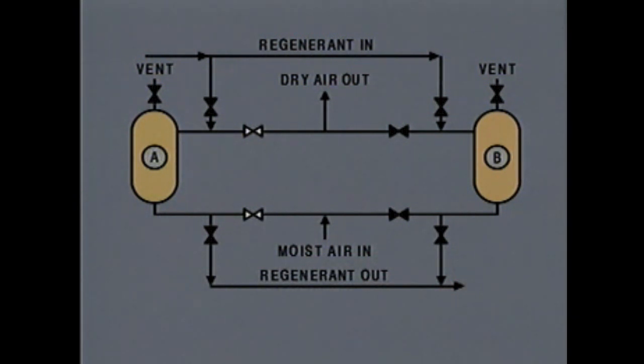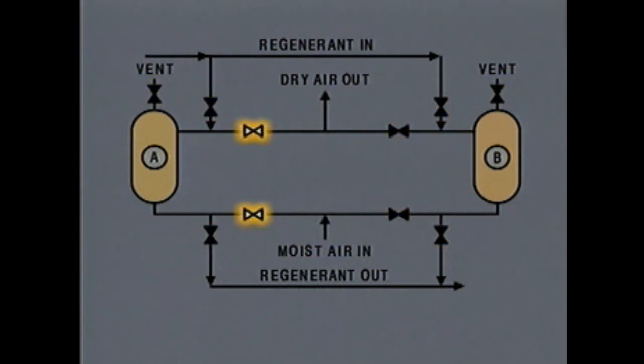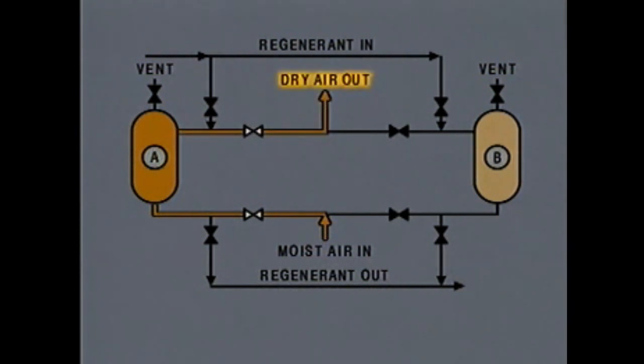This is how the valves are lined up when dryer A is in service. The filled-in valve symbols indicate valves that are closed, so only the remaining valves are open. Moist air enters the system and flows to the bottom of dryer A. Moisture in the air is trapped by the drying agent in the dryer, and dry air flows out of the system.